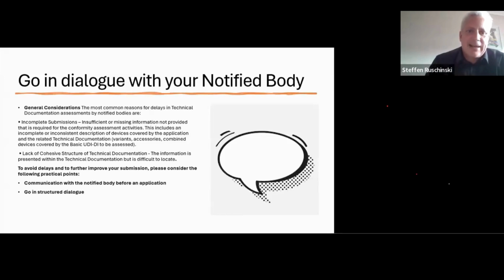The most common reasons for delays in technical documentation review by notified bodies are incomplete submissions, when insufficient or missing information is provided that is required for the conformity assessment activities. This includes an incomplete or inconsistent description of the devices covered by the application and the related technical documentation, or of variants, accessories, and combined devices covered by the basic UDI-DI to be assessed. It also includes a lack of cohesive structure of the technical documentation, where information is presented but is difficult to locate. To avoid delays and to further improve your submission, please consider the following practical points.